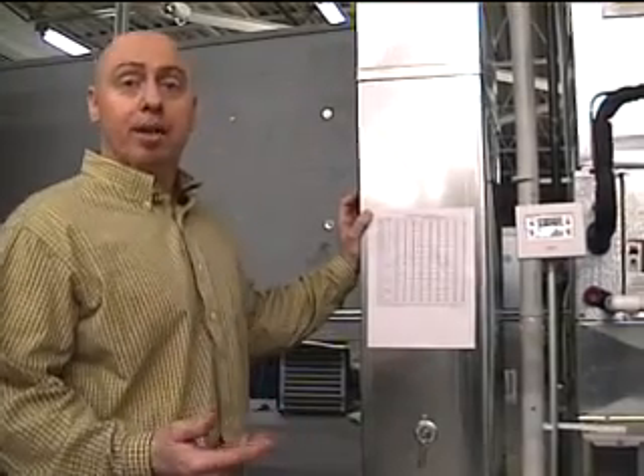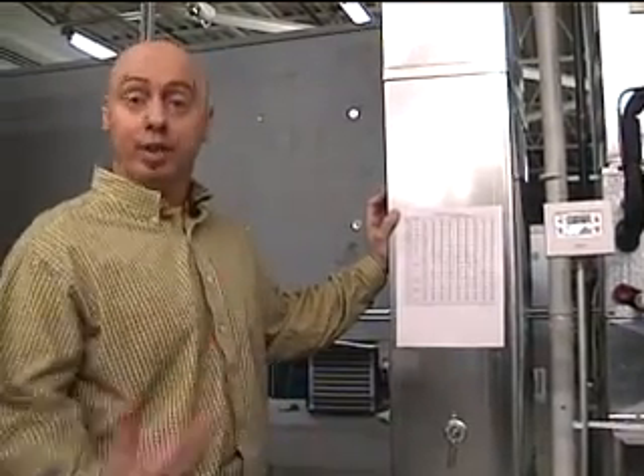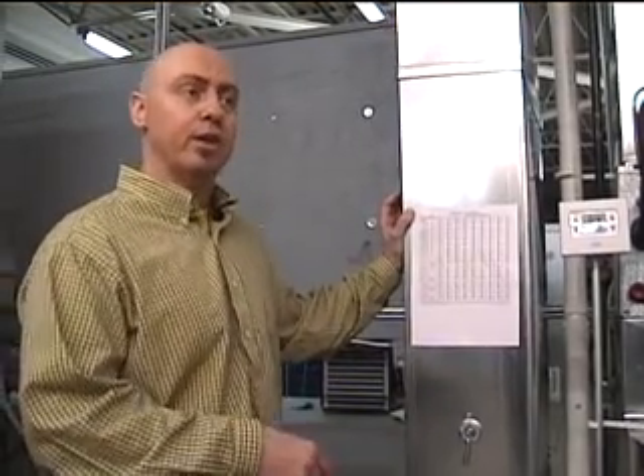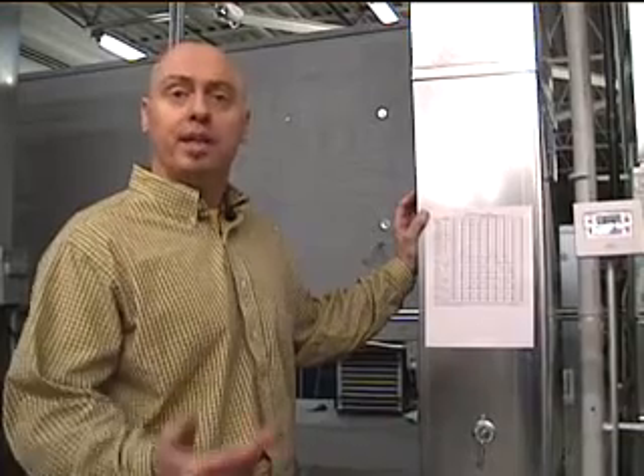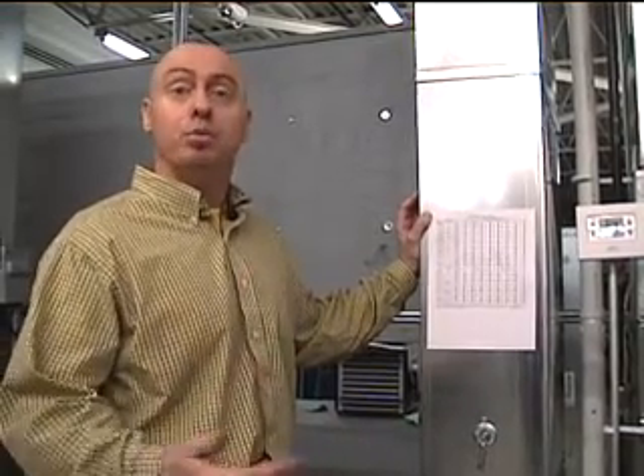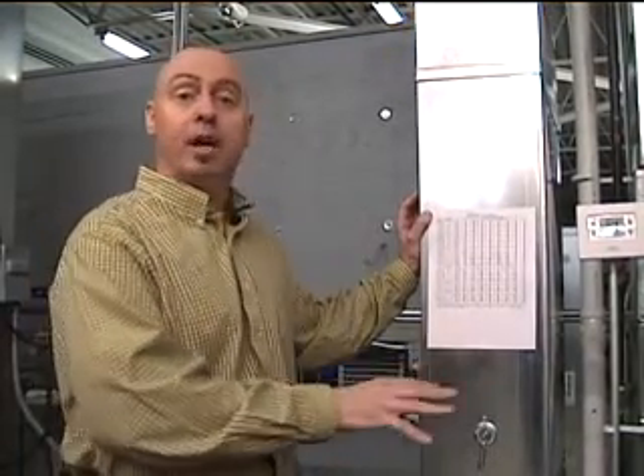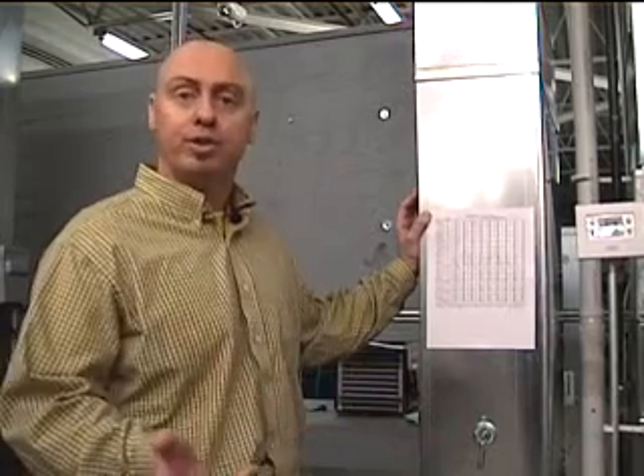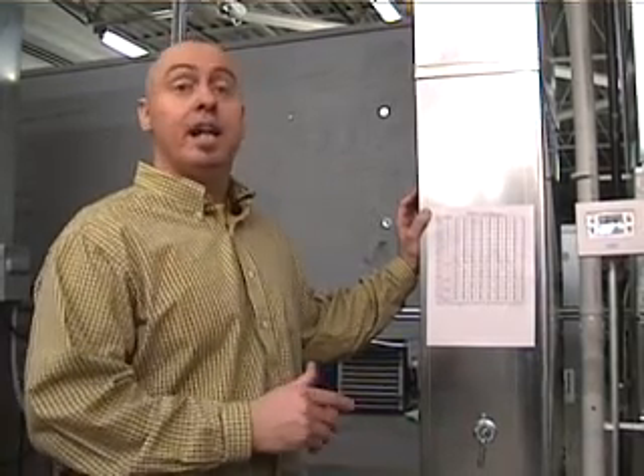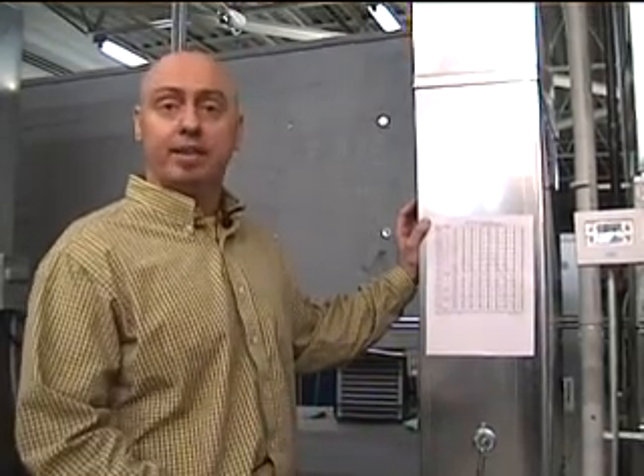Once you have your total static pressure, although you can evaluate your entire duct system by knowing the resistance value, you can also determine how much airflow you're actually getting. And that's actually a good number to know because a lot of guys assume a certain amount. Just because it has a blower drive saying 800 CFM, doesn't mean you get 800 CFM. Like I mentioned in the beginning, that only means you're getting that if you have the right static pressure.